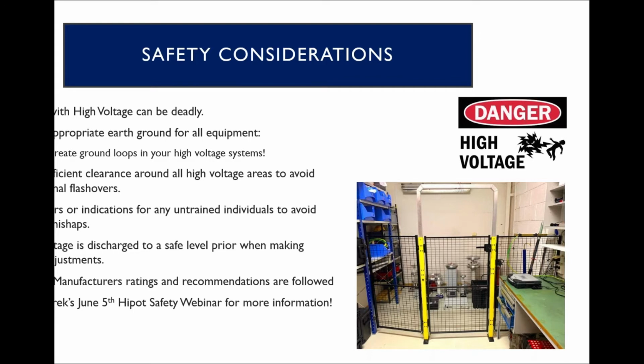You always have to ensure that there is sufficient clearance around all high voltage areas to avoid any unintentional flashovers. At higher voltages in really any kind of environment condition, the voltage will flash over in a much longer space than most people realize. At specific voltages, it might jump over a foot, for example. So really having that awareness and having that space gives safety to everyone. In order to really enforce that, the use of barriers or indications of high voltage areas for any untrained individuals would be beneficial to help avoid those potential mishaps. You don't really want an untrained individual walking through a space when there's 150, 300 kV right overhead without them knowing that that's there.